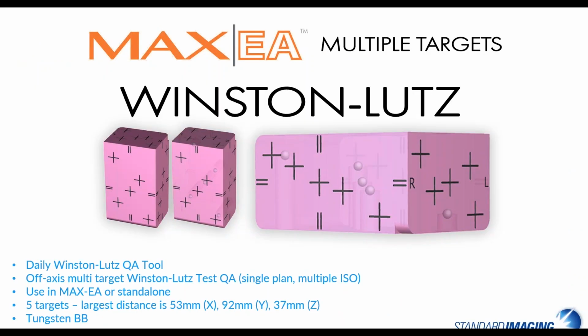So this is one of the targets. The insert that we supply with the Phantom is our multiple target Winston Lutz insert. So this has 5 targets, as you can see. It can be used in the Max EA, or you can use it by itself because we have the engraved crosshairs on the Phantom.